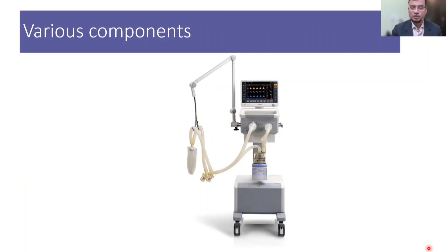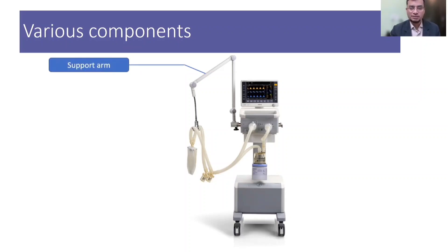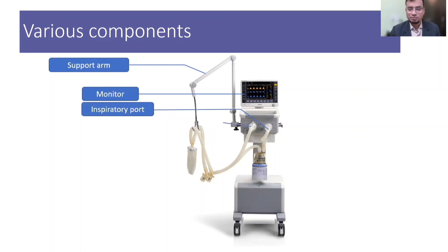Various parts of a ventilator and its connections are shown in this diagram. There is a support arm which is a metallic and flexible arm that supports and holds the ventilator circuit and protects it from kinking or damage. There is a monitor touch screen to display various controls and monitoring parameters. From the ventilator, gases come through to an inspiratory port and are driven back to the expiratory port, and both ports have inspiratory and expiratory valves.